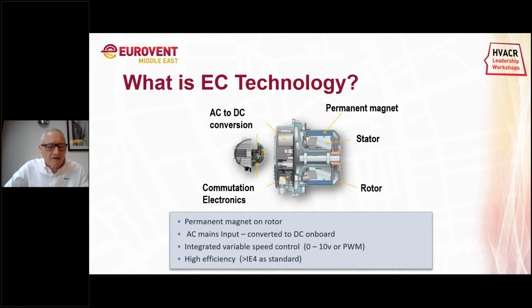DC motors rely on carbon brushes and a commutation ring to switch the current direction. With an EC motor, the mechanical commutation has been replaced by electronic circuitry that supplies the right amount of current in the right direction at precisely the right time for accurate motor control. We further simplify that by using a compact external rotor, as you can see here, with stationary windings and a permanent magnet inserted into the rotor.